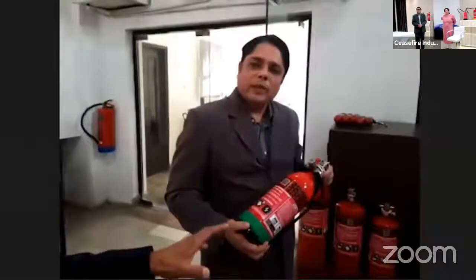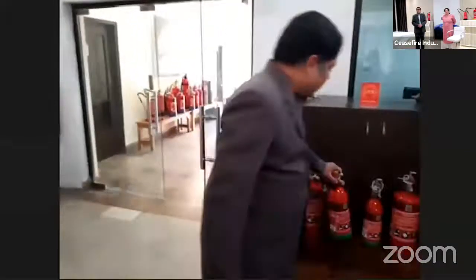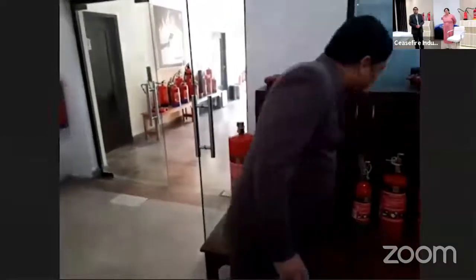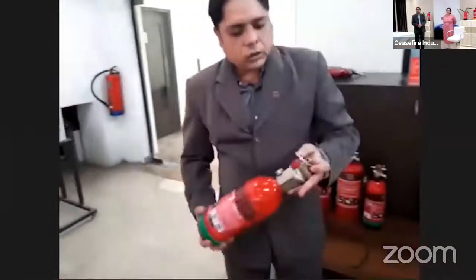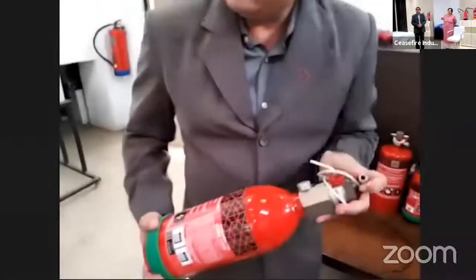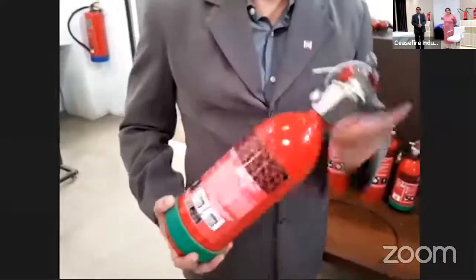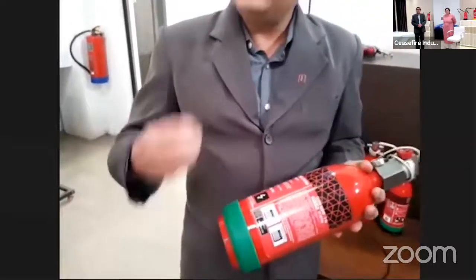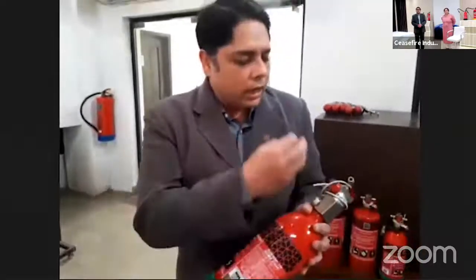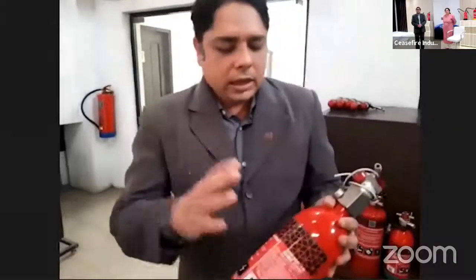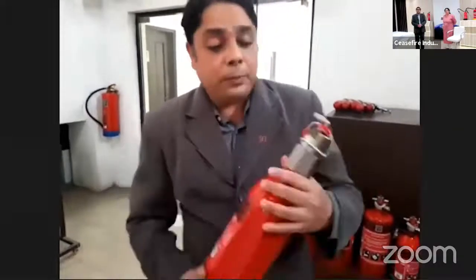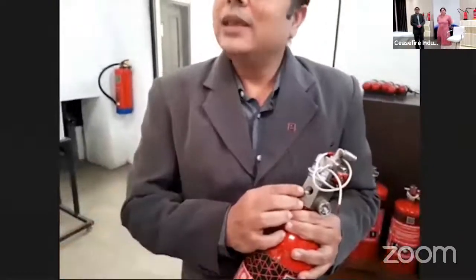The other version would be the indirect system, where the heat sensing tube is connected to the head of the valve. Here the tube just detects the fire and depressurizes, facilitating the opening of the valve, and the extinguishing agent then comes out through a separate port, which is quite bigger. So the discharge line is different. In this way, we can also use powder as an extinguishing agent.